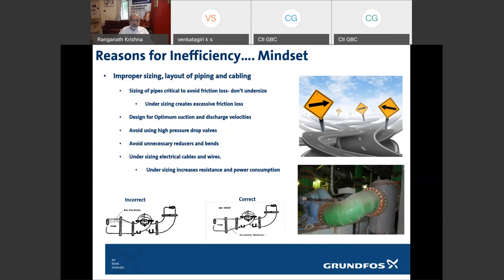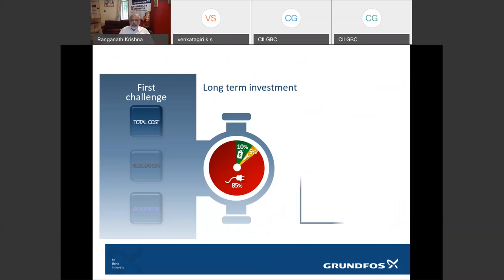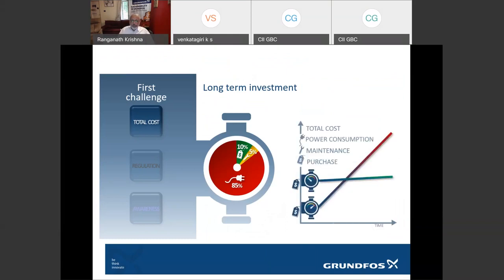Undersizing electrical cables: great savings by undersizing electrical cables. But again, like pipes, for the rest of your life, because of increased resistance, your power consumption is going to be much, much higher. So if you look at the life cycle of a pump, 10% is its initial investment, 5% is the maintenance cost through its life, taking a life of 15 years, and 85% is the power cost. So when you look at your next pump, when you're choosing it, please choose wisely and look at all the areas. Don't look at the pump only on its own. Look at your entire system: your piping, your equipment, your valves, the way you're taking your piping around, what kind of pressure drops. Look at the entire system.